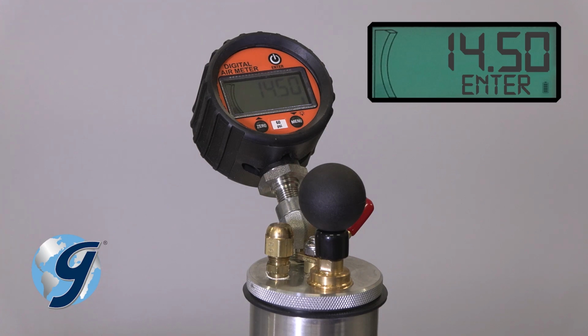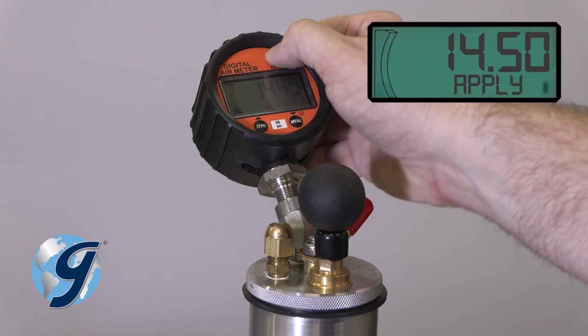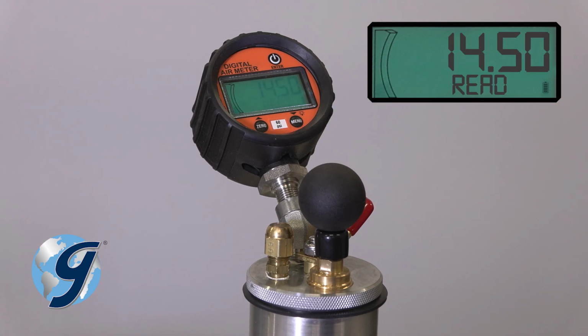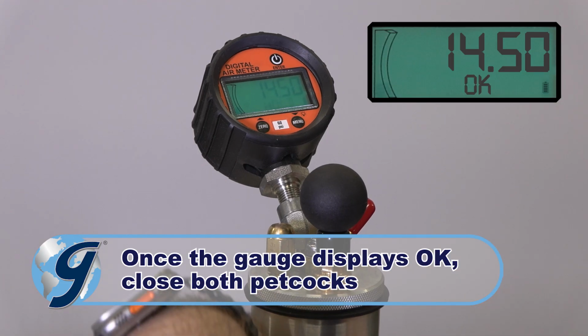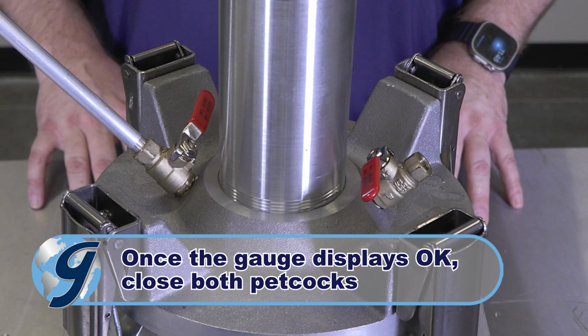Press Enter and the gauge will display OK. The gauge will display high or low if the reading is off. Adjust pressure as necessary, then press Enter. Once the gauge displays OK, close both petcocks.